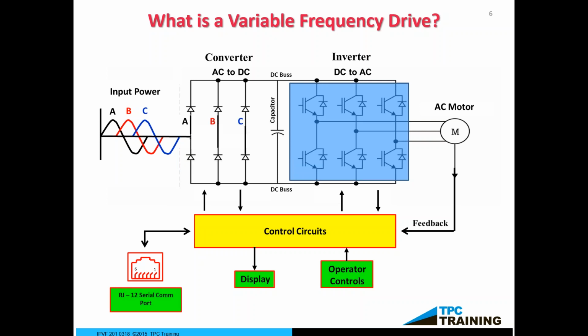As you can see there, below in the yellow, you have control circuits. If you saw the tails on those transistors, that's the vertical line just opposite of the arrow there. Those tails or those control circuits, or let's call them firing circuits, go down to the control circuits, and that's what gives us our speed control. As much as we mentioned earlier, as much as we turn those inverters on and off, that's where the control circuits come into play.